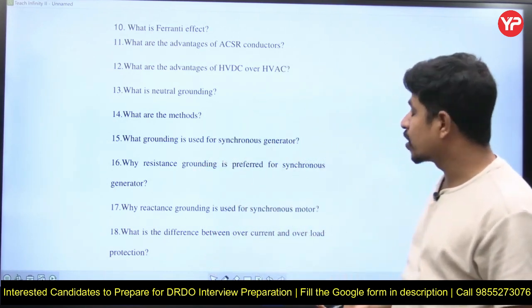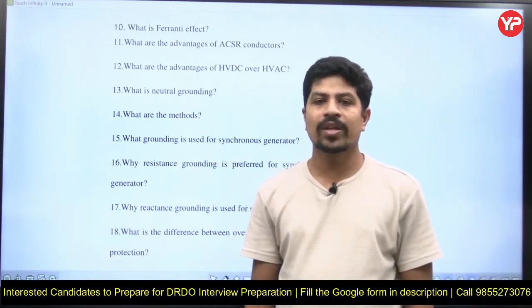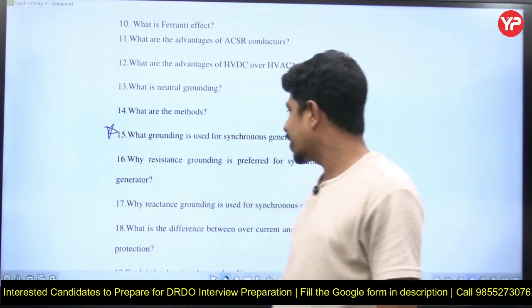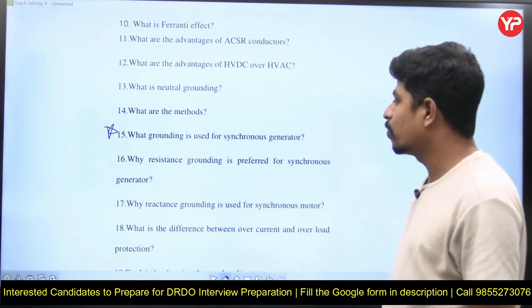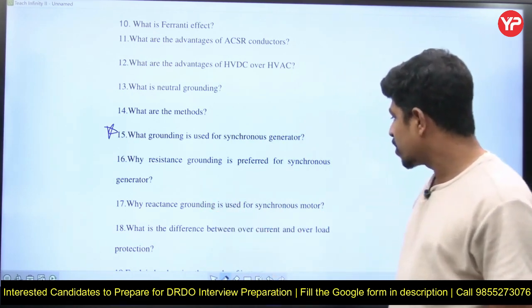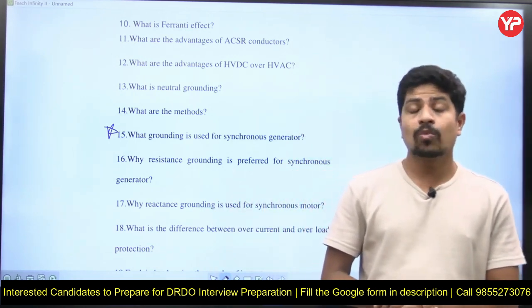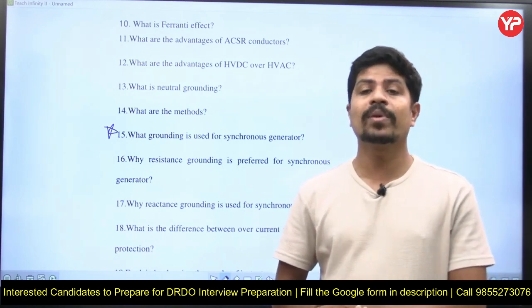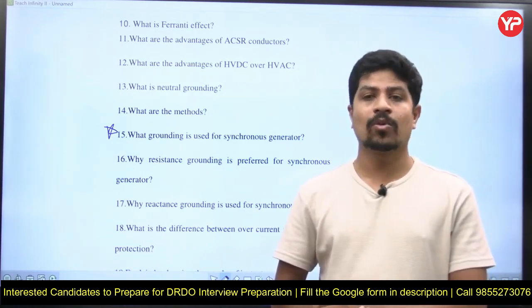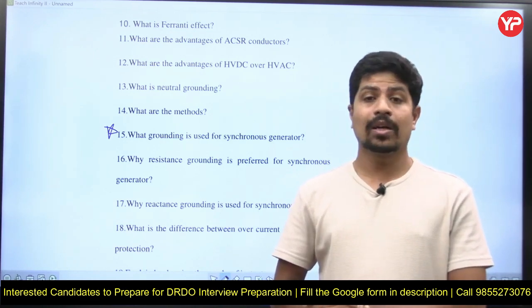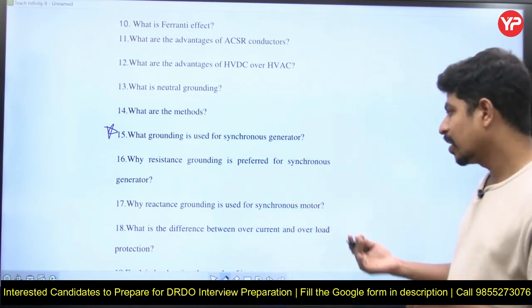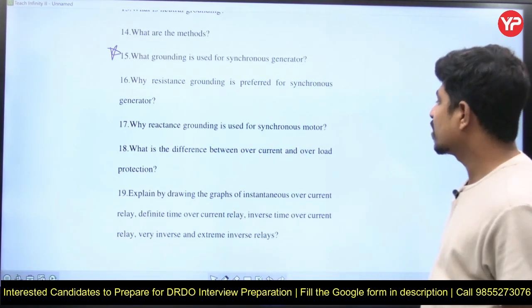What grounding is used for a synchronous generator? Resistance grounding is used for synchronous generators to improve power system stability. This is a very good question. Why is resistance grounding preferred for synchronous generators? To improve power system stability. Why is reactance grounding used for synchronous motors? Synchronous motors mostly operate at overexcited conditions; if overexcited, there is excess reactive power, so an inductor connected from neutral to ground — reactance grounding — absorbs that excess reactive power.